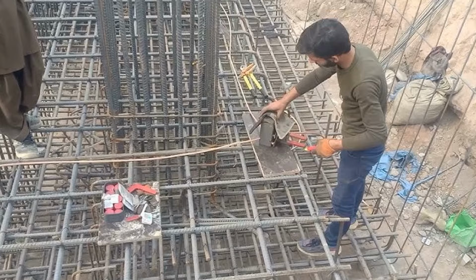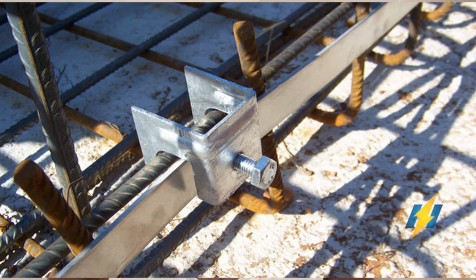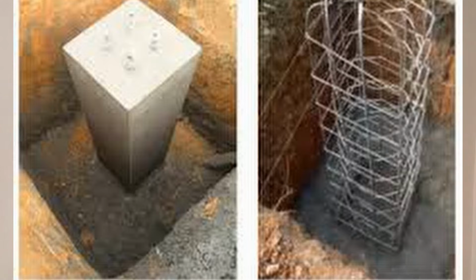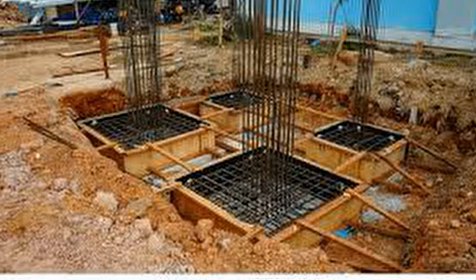You bring the down conductor to connect to that foundation earth. All metal services, if you have any metal pipe work, staircase, balustrades, handrails, water tanks. Okay, water tanks are typically not metallic in Ghana, so that's fine. But anything metallic, you connect to the foundational earth system. The foundational earth system is connected to the steel reinforcement rebars, right? Which, I'll show you a picture, are laid above the foundation soil before the concrete is poured. Don't forget the columns that are going up the building also have rebars in them. They connect to the same rebars in the foundation, right?